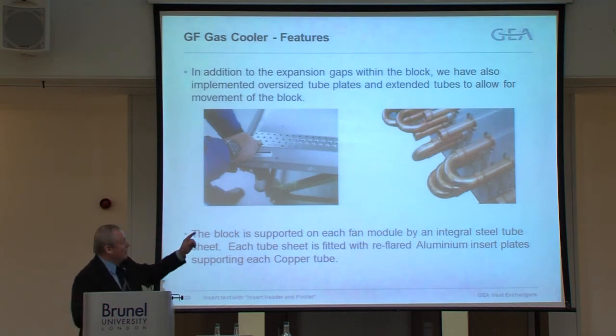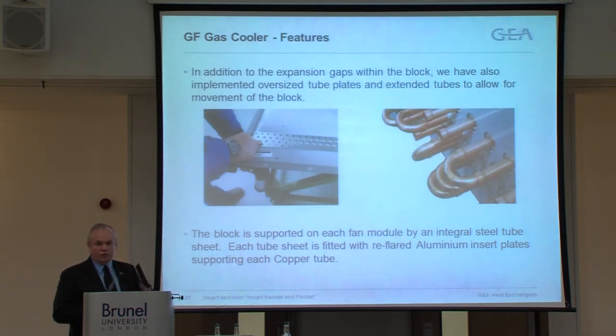places. To further minimise the effect of expansion and contraction, we make the tubes that stick out at the end of the matrix about twice as long as we normally would. And that is really to take the joint away from the fixed point so that any expansion and contraction sideways doesn't actually compromise the joint.